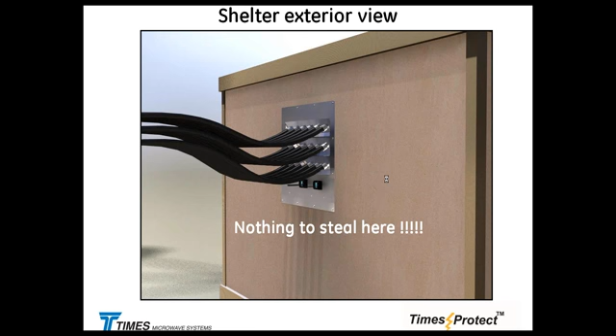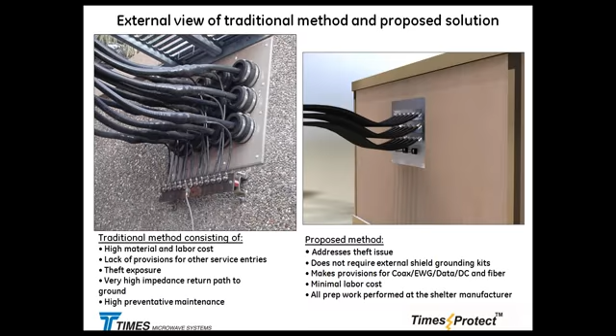You might be asking, Bogi, where is the master ground on the outside? Well, we don't have it on the outside. Why encourage somebody to steal it if we have better options for grounding? If you look at the traditional method, there's a trapeze with all the protectors mounted on it, an internal master ground bar, and another ground wire going to the ring ground around the shelter.